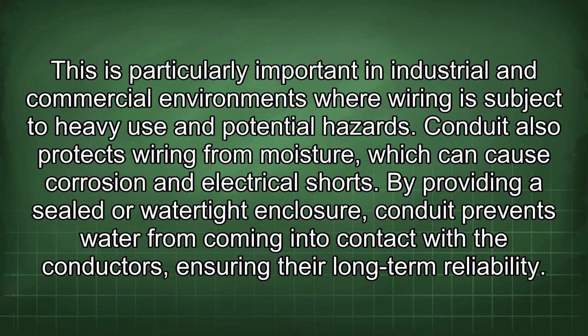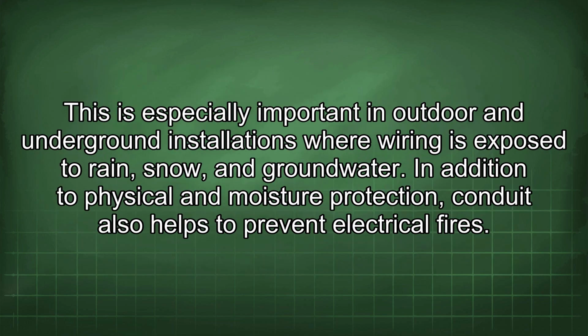Conduit also protects wiring from moisture, which can cause corrosion and electrical shorts. By providing a sealed or watertight enclosure, conduit prevents water from coming into contact with the conductors, ensuring their long-term reliability. This is especially important in outdoor and underground installations where wiring is exposed to rain, snow, and groundwater.